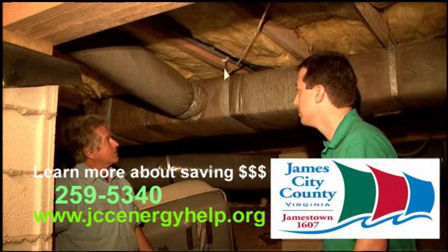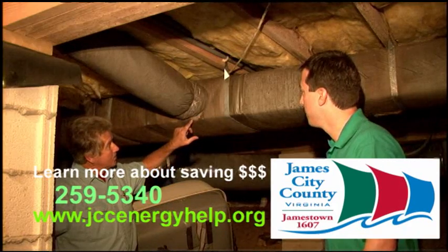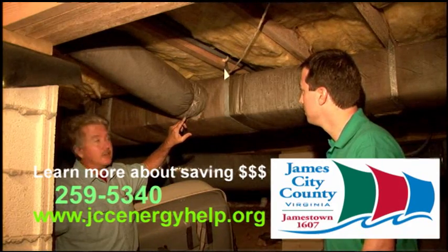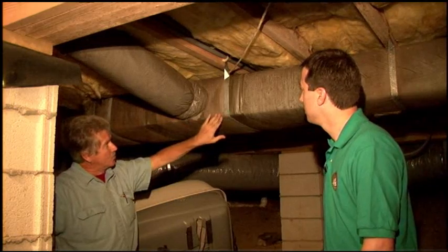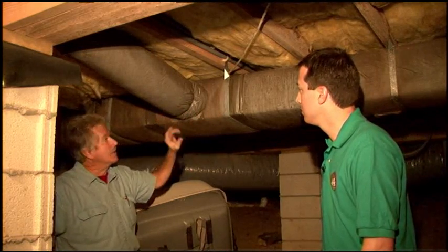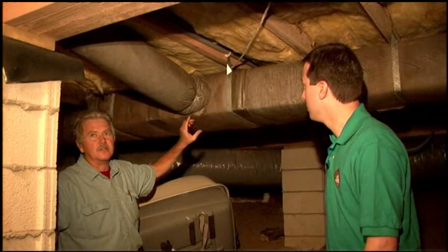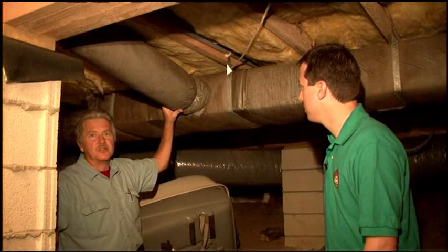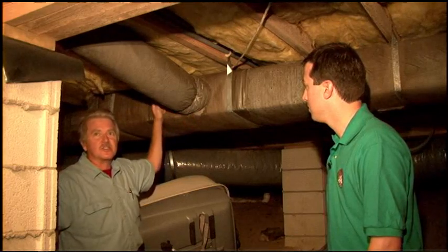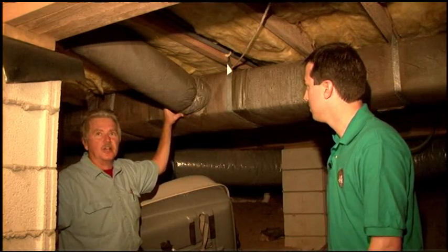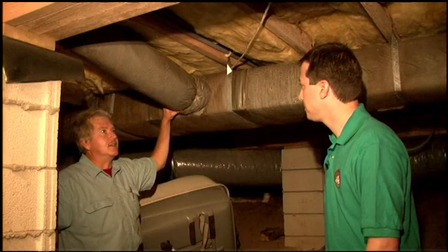Now, with respect to the ducts here, you may see right here where this is washed clean. This duct has been leaking right here. There is a joint between the trunk line and this takeoff here, and there's air blowing right through that joint right there. When that cold air hits the warm moist air under here, it condensates like rain, and then it washes off the dirt that's on the outside of this duct here. So what we need to do is to pull this insulation back here and mastic seal around that joint, seal the duct to the collar with mastic, and then go ahead and close that back up.